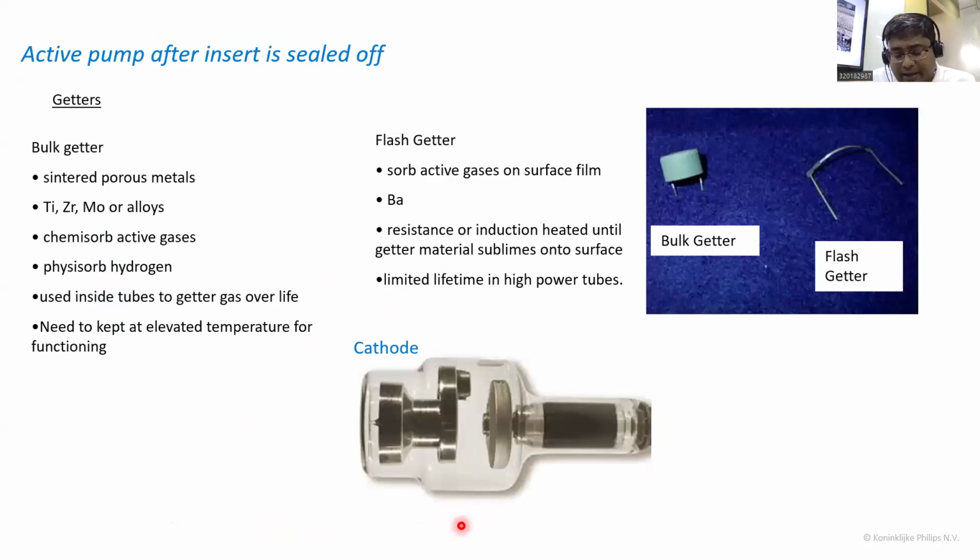So like I say, for long duration applications where X-ray is produced for a considerable long time, the temperature inside this vacuum tube, all this metal component, is elevated. How much?